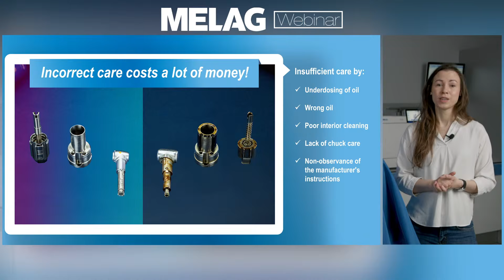And of course, another problem would be, it's good if you lubricate the instruments, but it's really bad if they are not cleaned from the inside well enough. So poor interior and exterior cleaning could be one of the reasons, as well as, you mentioned it already, the chuck care. It's very important that also the top part of the instrument is cared for and not just the inner channels. And lastly, of course, it's really important to always check what the manufacturer of the instrument recommends for the instrument to make sure that they have a long life. Yeah, right, indeed.